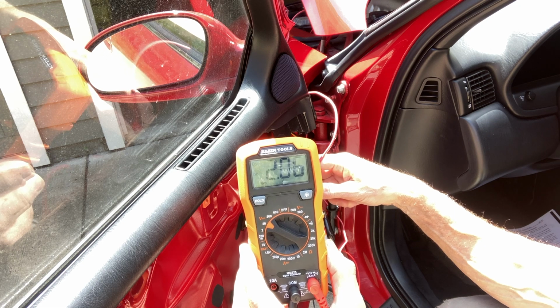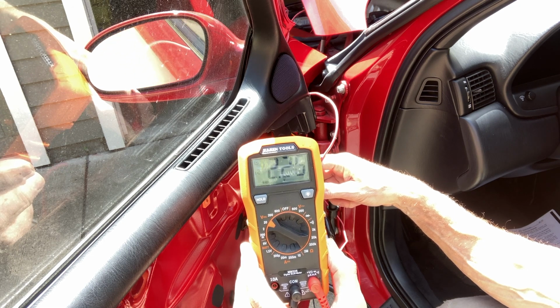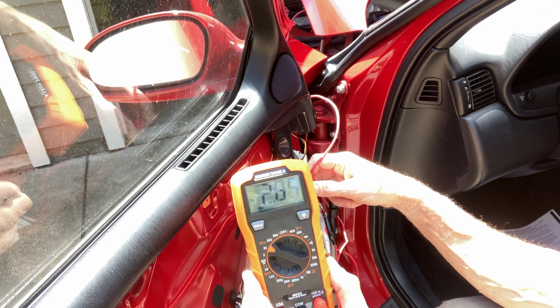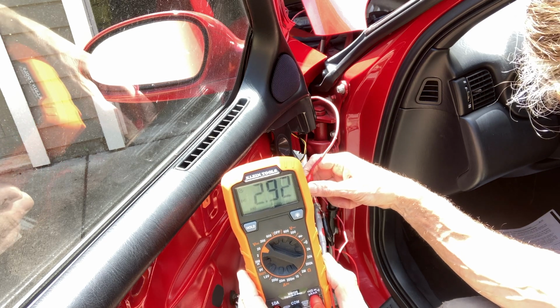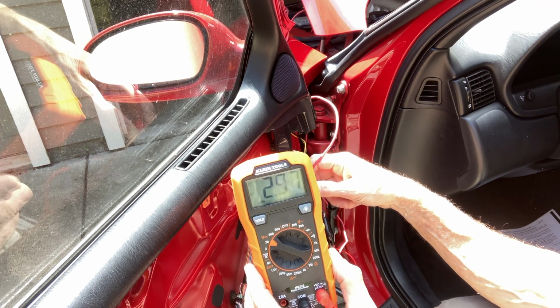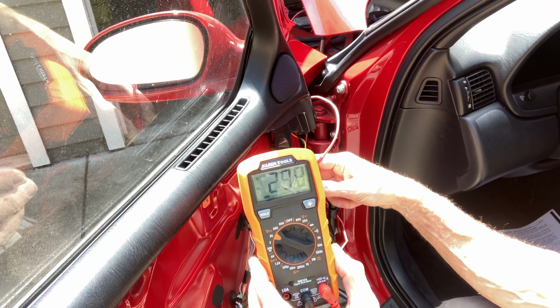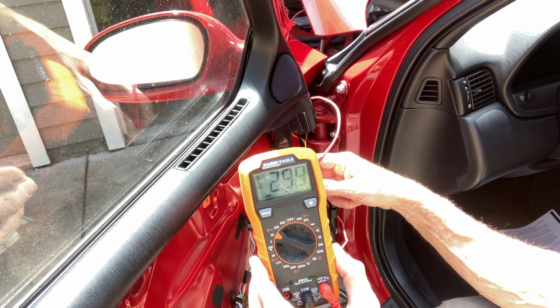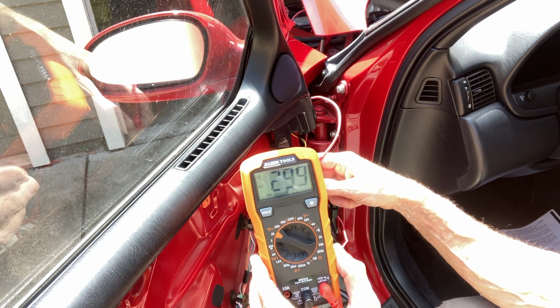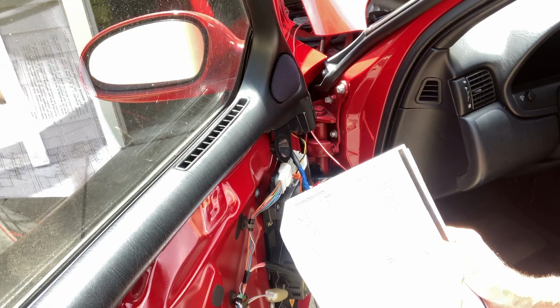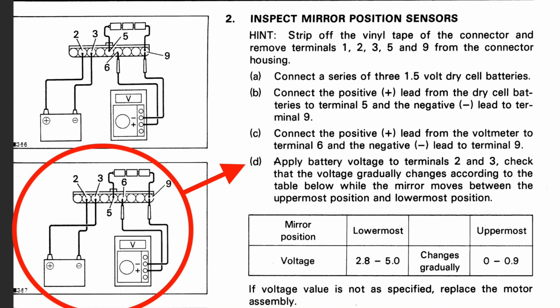So our voltage is going up, up, up. It should go as high as 5 according to the instructions. And it just stopped at 2.99. It's in range, that's what we're looking for. It doesn't explicitly say to reverse the polarity here. It just says apply voltage to terminals 2 and 3. And I guess it means both ways, and check for these numbers.